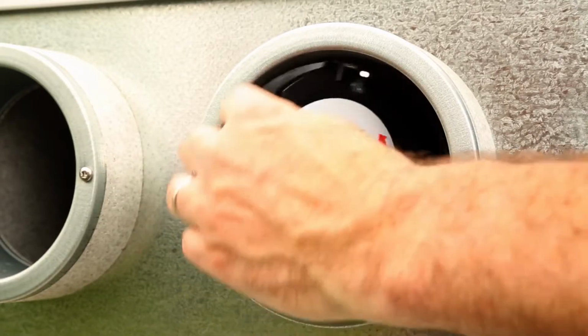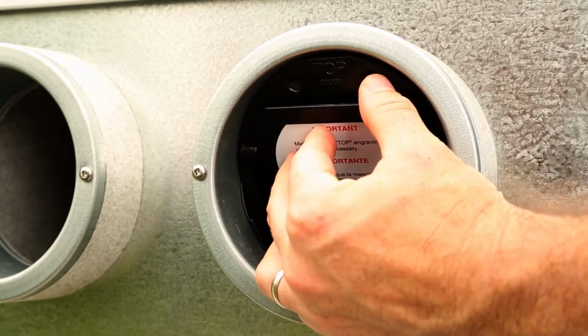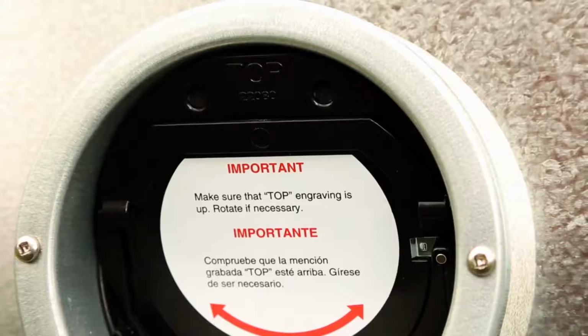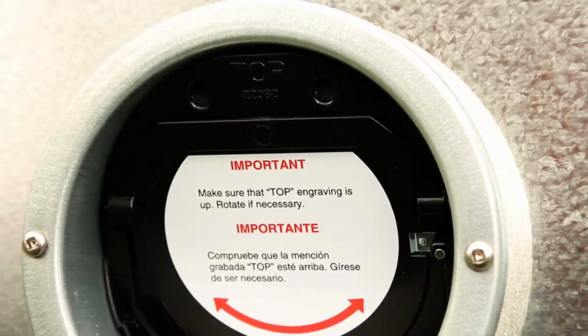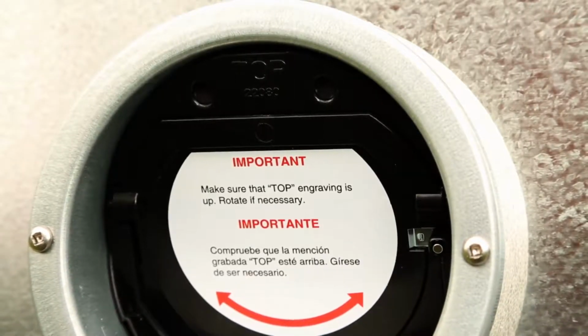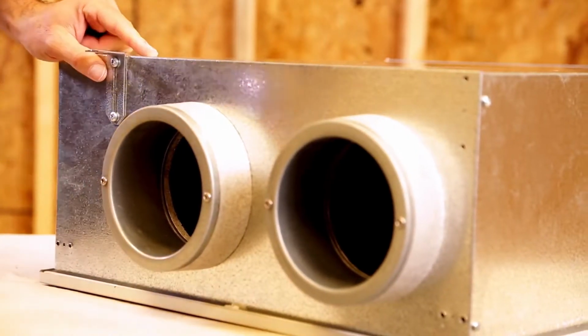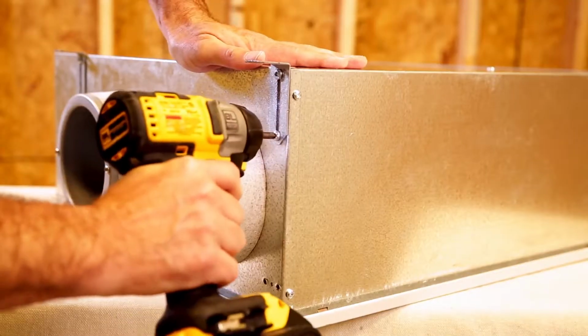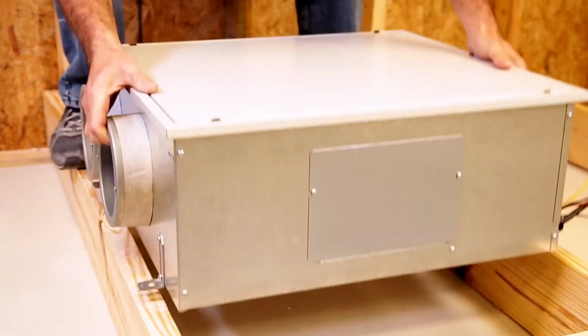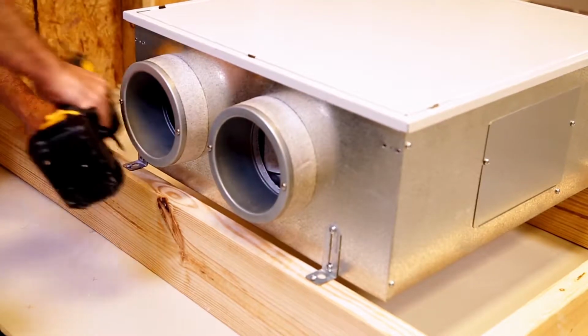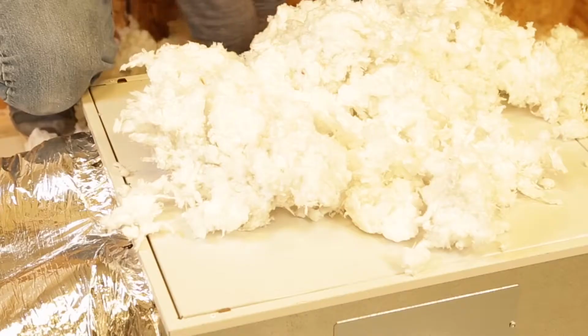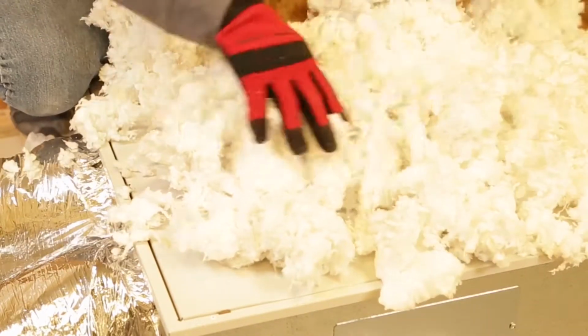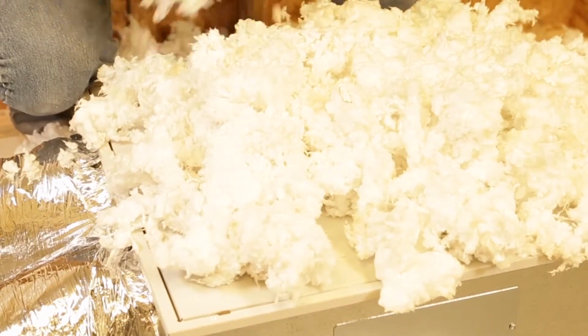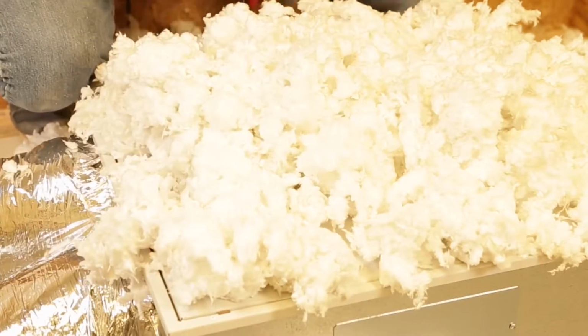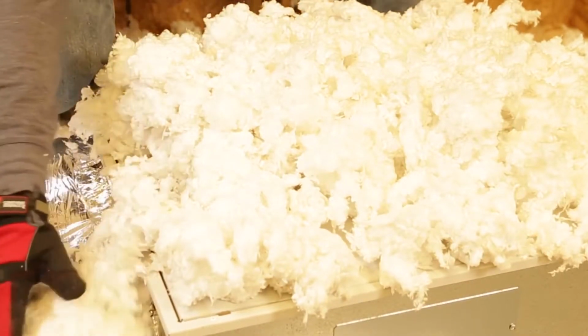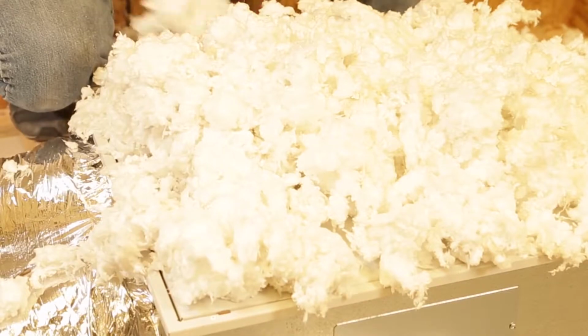To install the ERVS100 in the attic, first rotate the backdraft damper 180 degrees so that it falls in the closed position and the word top engraved on the damper is facing up at the top. Mount the brackets to the bottom corners of the unit using two number 10 by 5/8 inch screws per bracket. Secure the unit to the top of the trusses using one number 8 by 1.5 inch screw for each bracket. For the in-ceiling and attic installations, if the attic is not ventilated and without radiant barrier sheathing, apply insulation material around and over the unit. Just be sure to allow access to the unit door for maintenance.